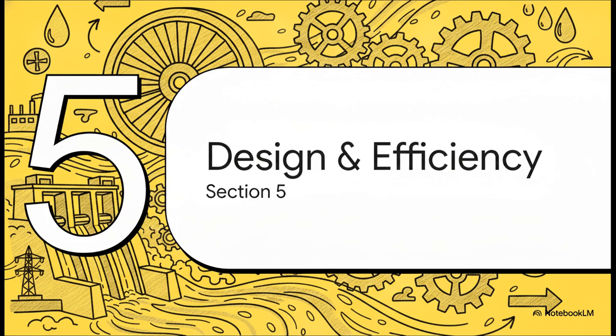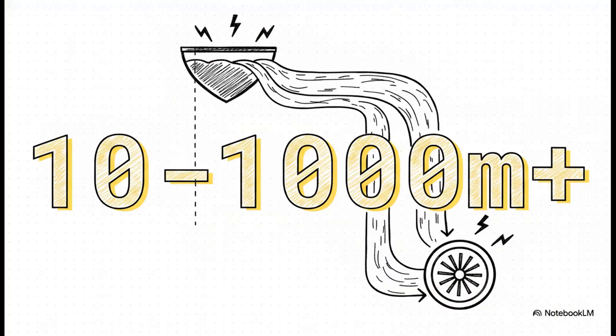Now, let's take a quick look at the typical design data to truly understand the macroscopic scale, scope, and performance of the systems we just explored. Remember when we talked about the hydraulic head earlier? Well, the vertical distance the water falls from the reservoir down to the turbine can be anywhere from a relatively modest 10-meter drop to a massive gravity-fueled plunge of well over 1,000 meters. It's a simple rule. The greater the head, the greater the pressure, and generally, the more power you can extract from a given volume of water.